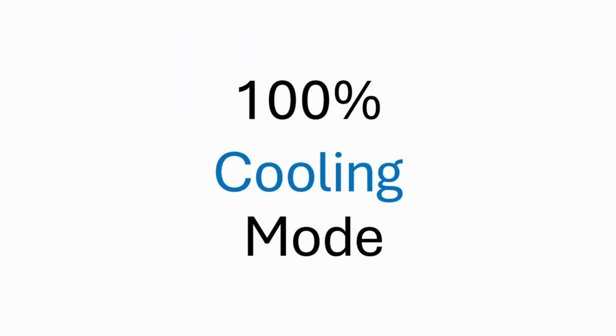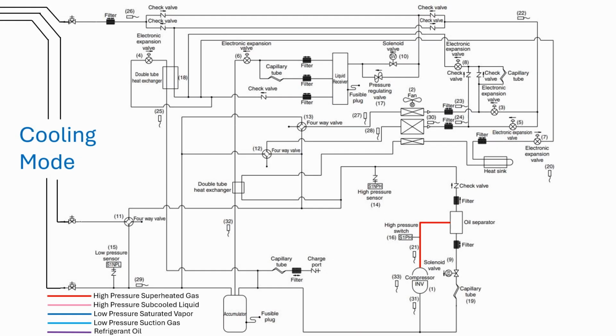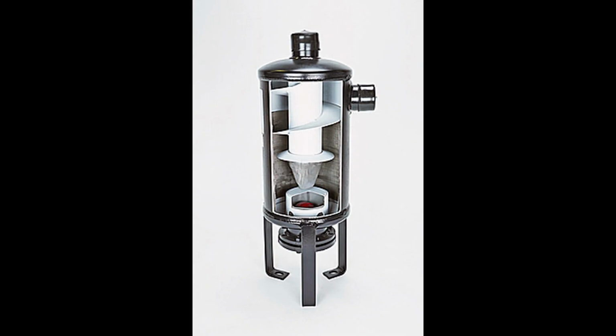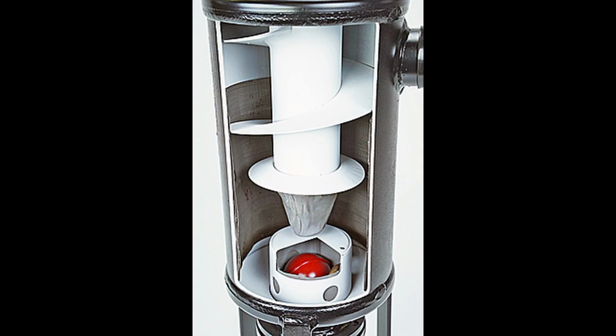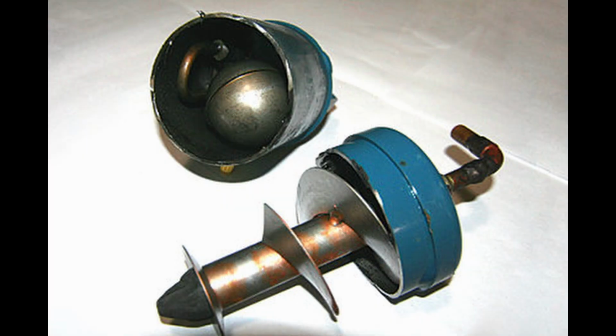This system is in 100% cooling mode. The refrigerant leaves the compressor as a superheated high-pressure vapor. Its first stop is the oil separator. The oil separator is a spiral device that uses centrifugal force to separate the oil from the refrigerant as it leaves the compressor. Then it returns the oil back to the compressor where it belongs.